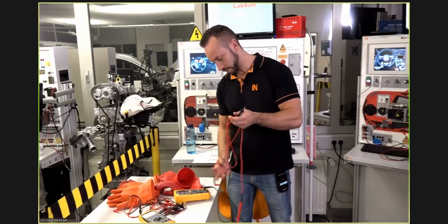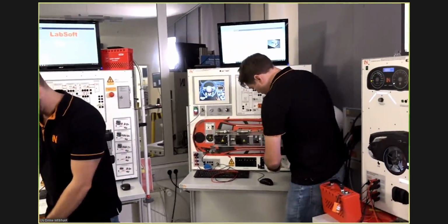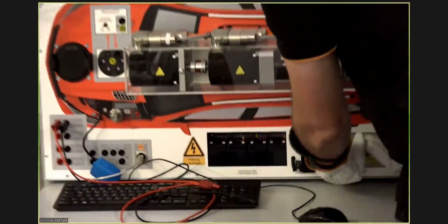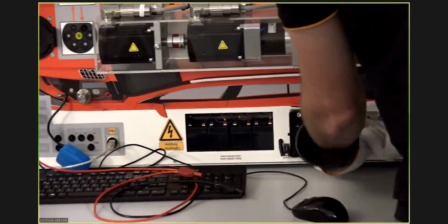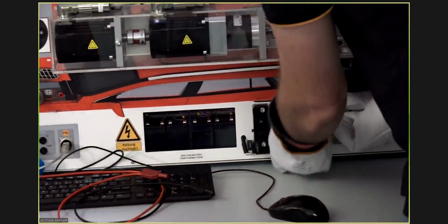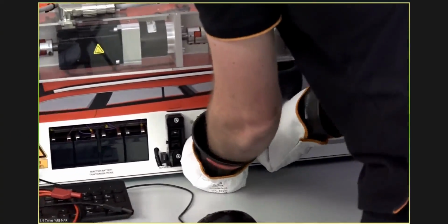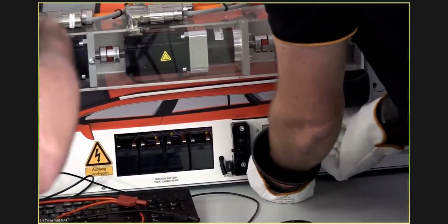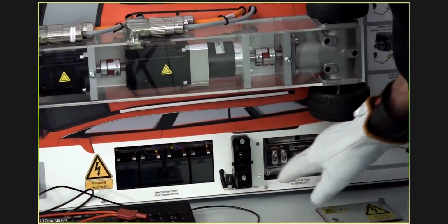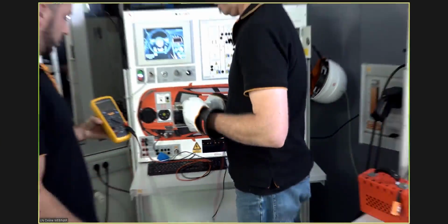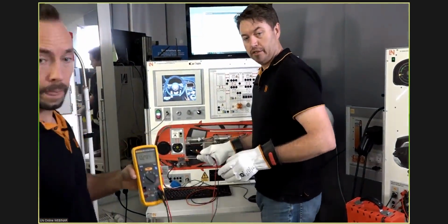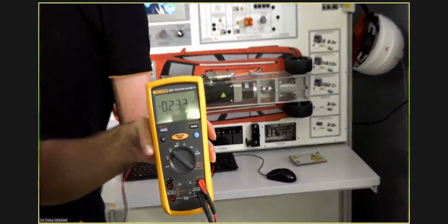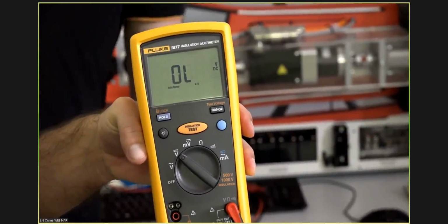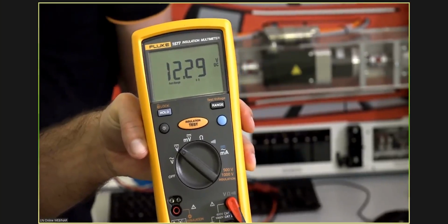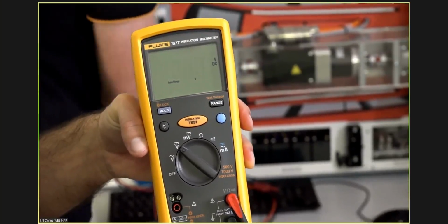What I'll show you here is I'm going to remove the high voltage inspection point. Because I don't know if the system is free of voltage yet, I'm using the high voltage gloves. At this point here are our two little terminals for the battery. We'll show that to the camera. What I'm going to do is go down here to the battery. This is the 'live' of our live-dead-live test, so I'm testing on the battery here.